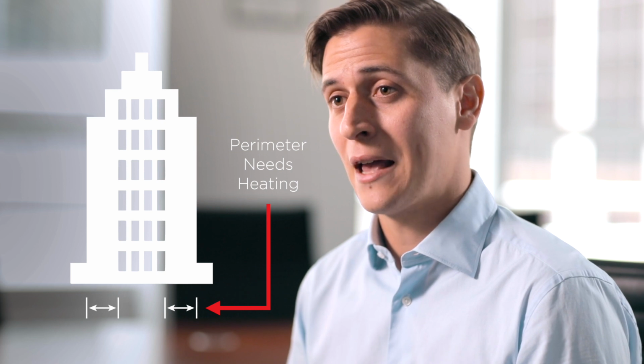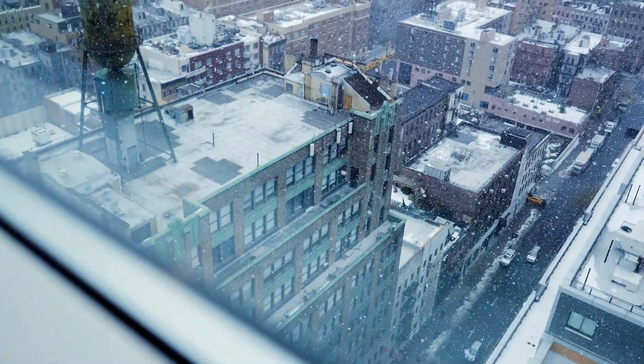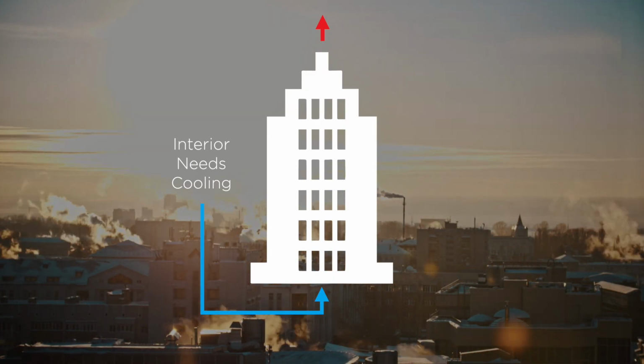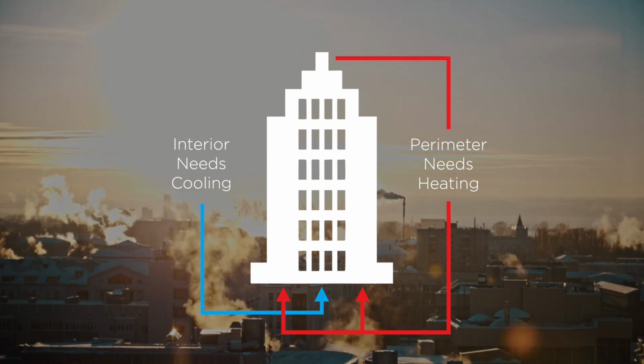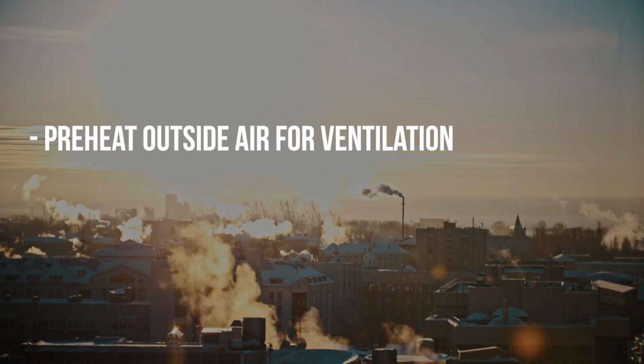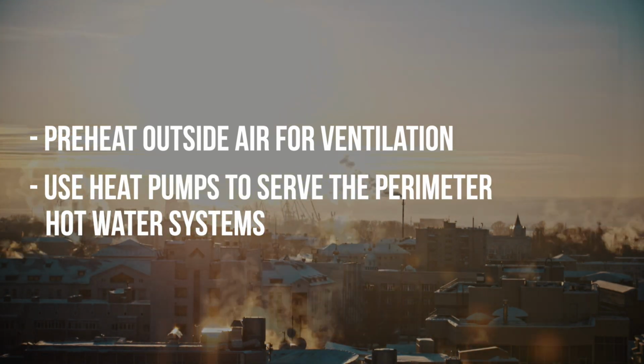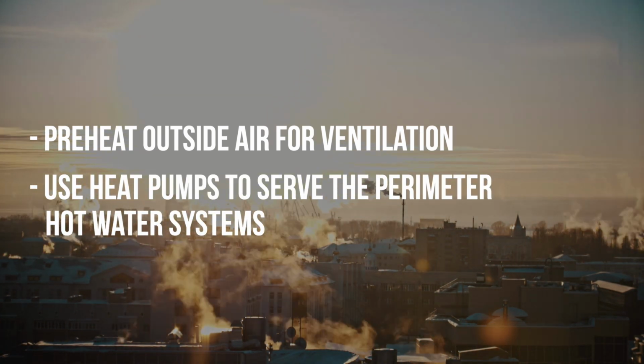At the same time, you're using fuel oil, natural gas, or Con Ed steam to provide heat for the perimeter. So what if instead of rejecting that heat from the interior and sending it out the cooling tower, we made use of it? We could use it to preheat outside air needed to ventilate the building in winter, or lift it to a higher temperature using heat pumps to serve the perimeter hot water systems. We did an analysis for one office building and found that 30% of their heating energy use could be reduced by recovering the energy they were sending out through their cooling tower in the winter.